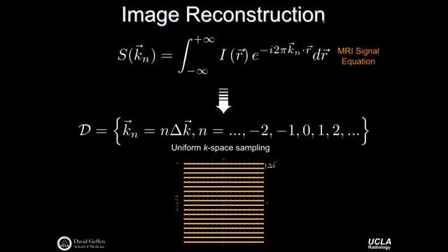If we look at this spatial frequency encoding term here, we actually do something with regularity in Cartesian imaging. We're always thinking about the same step sizes. We always have delta k's that are determined by our chosen field of view, right? Field of view is 1 over delta k. We pick our field of view, delta k is fixed. And that dictates that the k points that we actually care about are just n multiples of some delta k, where n is just a bunch of integers that move us through the specific and discrete lines of k-space, for example. So we're just saying that the space that we care about is actually a bunch of discrete k-points or k-lines that can be mapped out according to some delta k that we specify. Delta k is linearly and specifically related to the field of view.